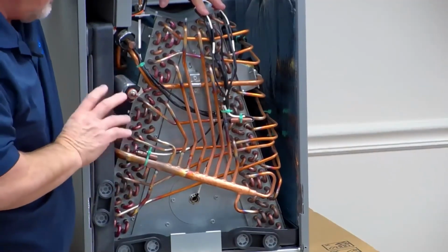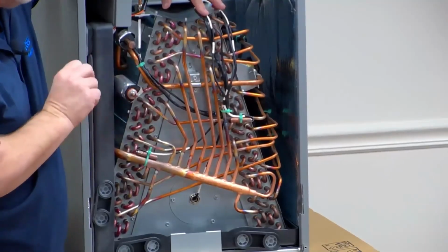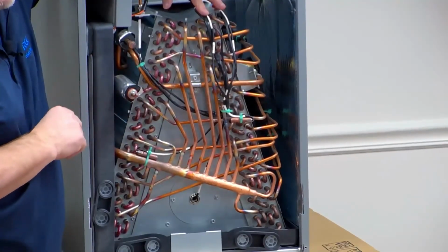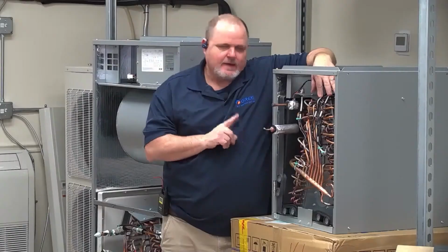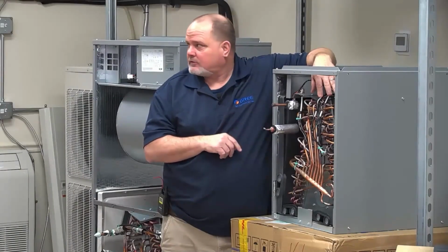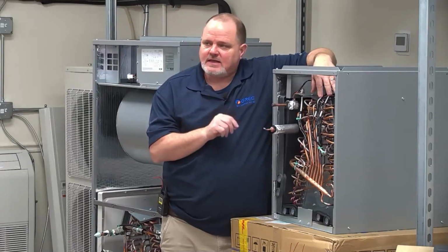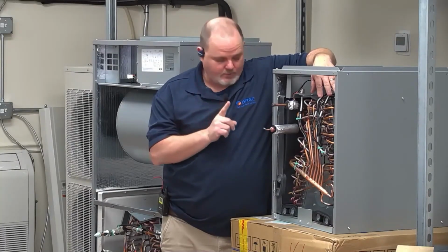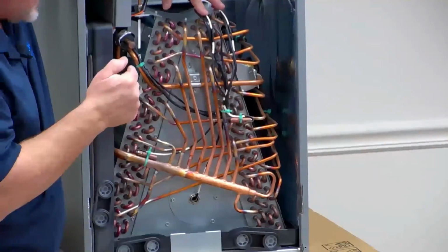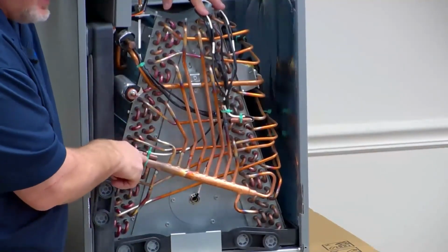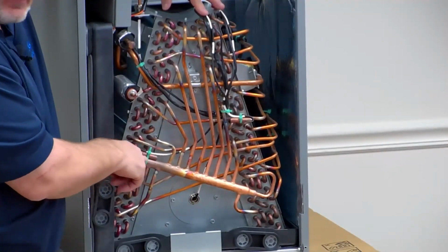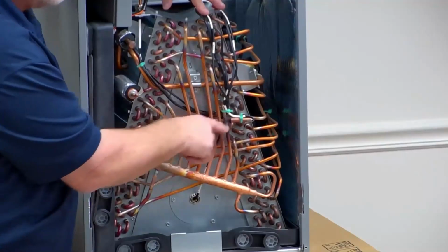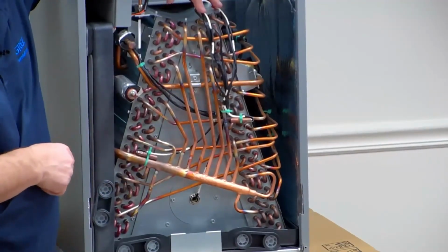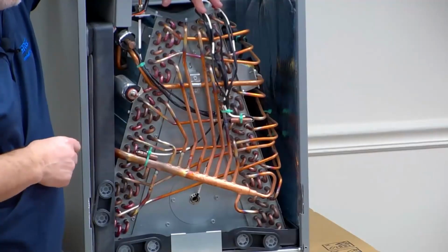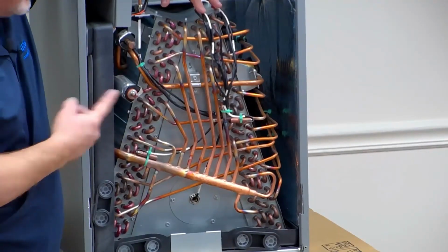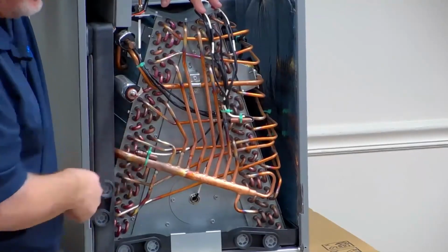The one thing that I want to point out to you, make sure you realize, is on the service tool, they are marked as inlet and outlet pipe temperature sensors. If you're in heating mode, that's backwards. Because in the tool, it still says inlet and outlet. But remember, you're flow reversed. So now we're flowing hot gas into here. So now your outlet temperature sensor becomes your inlet temperature sensor, and your inlet becomes your outlet because your refrigerant is flowing the other way. So you got to keep that in mind when you're in heating mode. Inlet and outlet are reversed. In cooling mode, that is your inlet, that's your outlet.